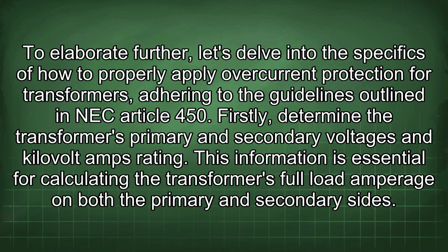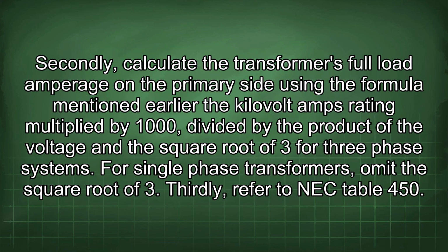This information is essential for calculating the transformer's full load amperage on both the primary and secondary sides. Secondly, calculate the transformer's full load amperage on the primary side using the formula mentioned earlier: the kilovolt amps rating multiplied by 1000, divided by the product of the voltage and the square root of 3 for three-phase systems. For single-phase transformers, omit the square root of 3.